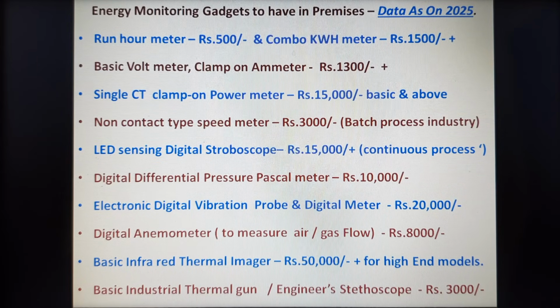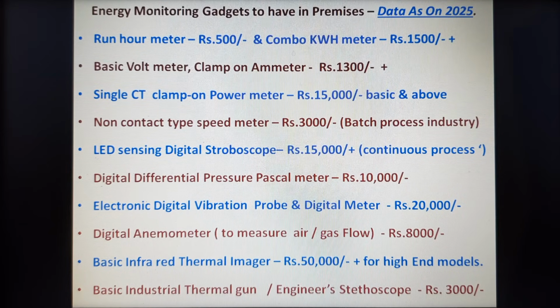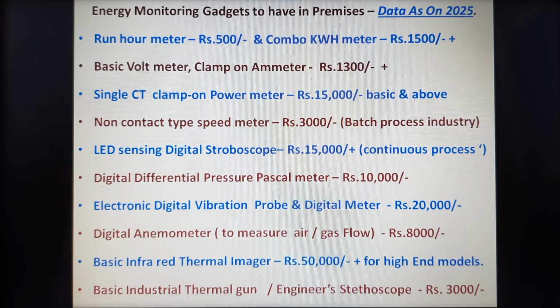It just costs around 10,000. It's a digital Pascal meter to know about the blower efficiency. For the given flow, if the static pressure is going higher and higher, you are supposed to keep around 600 pascals for your blower. If you are keeping around 1000 pascals, definitely the power loss is around 30% there. So let us see what Pascal we have to maintain to optimize the process.